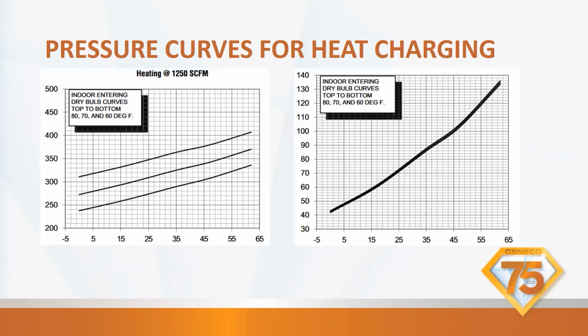So I've got a question on here. I've been told suction pressure is not a great tool for diagnostics because the expansion valve can adjust even if the charge is low. That is correct. So what we're talking about here is pressure curves for the high side. And again, the low side is just there for reference, so that when you're checking your high side, if you look over there and you see that your low side's all the way down to 30 or 0, you know something's going on. You know, your TXV or whatever is not working right, something like that. Okay. So it's just there for reference.